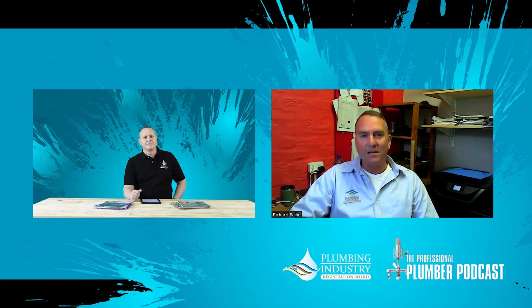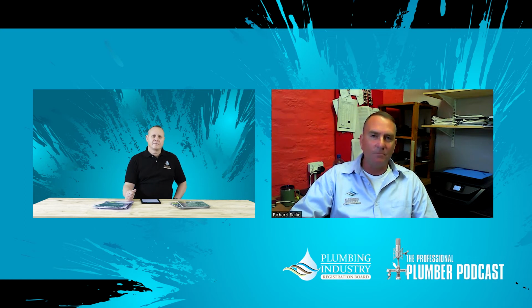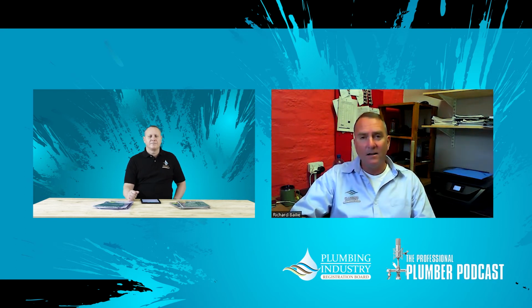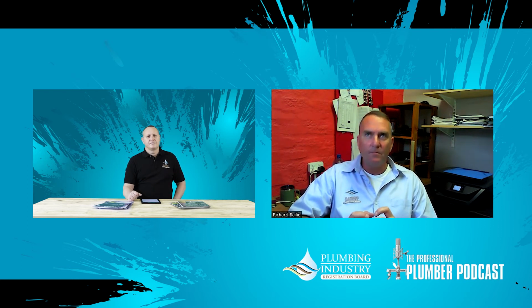And so a small detail like that goes to give heat pump systems very, very bad names. I've heard people in utter disgust of heat pump systems say, well, this just simply doesn't work. And it's not the fact. The fact is that it hasn't been installed correctly. So particularly with heat pump systems, there is a very real concern that one needs to conserve the stratification layers within the tank when you install a heat pump. I hope I've explained it properly.